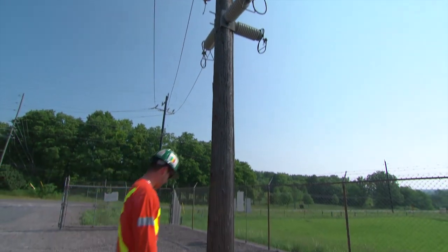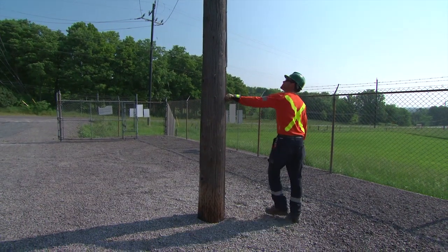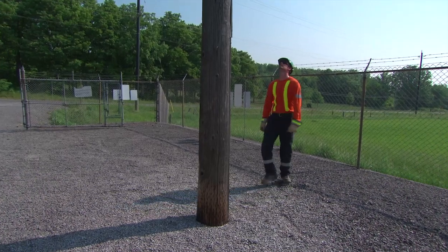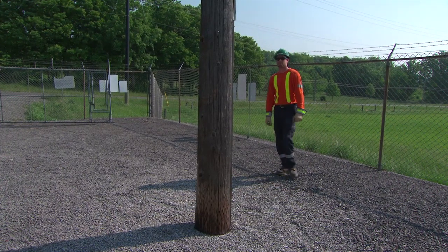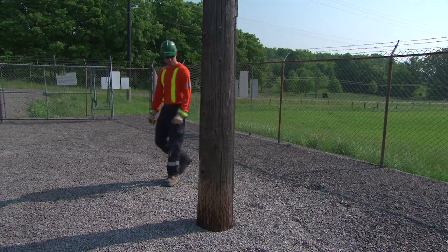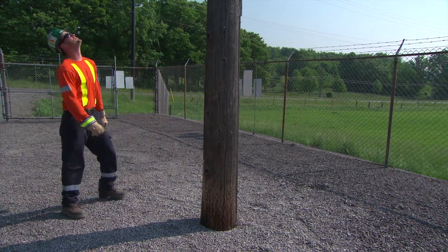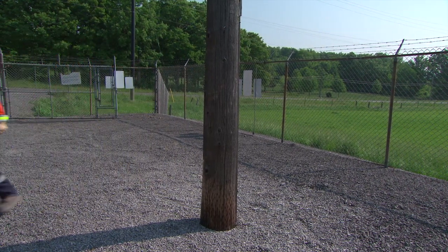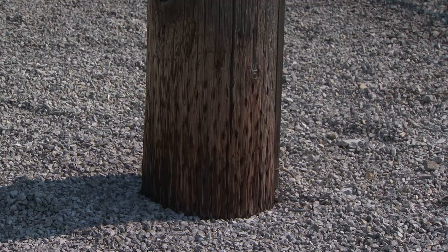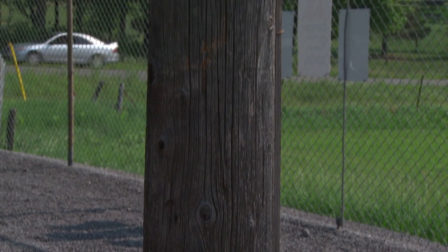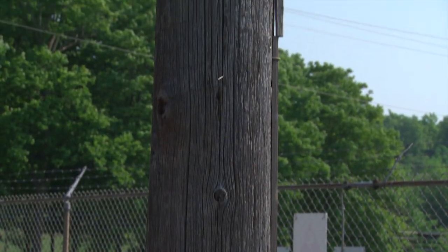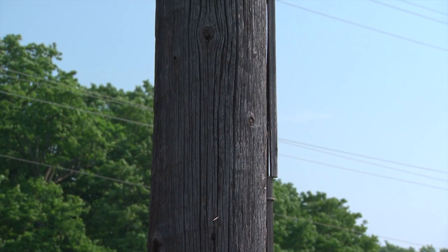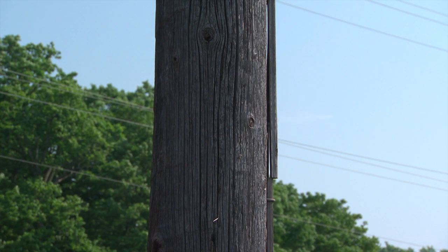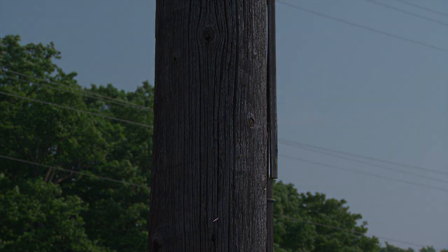Check for severe cracks or rot on the first wood pole structure within the station, as well as the first wood pole outside of the station. These poles must be able to support the added weight and stress of the low-voltage cables. A good indication of a bad pole is if the top end has deteriorated due to age and weather. You can also tap the pole with a hammer to listen for hollows or voids. If you find severe rot or damage, stop the job and contact provincial lines to inspect the poles and replace them if required.